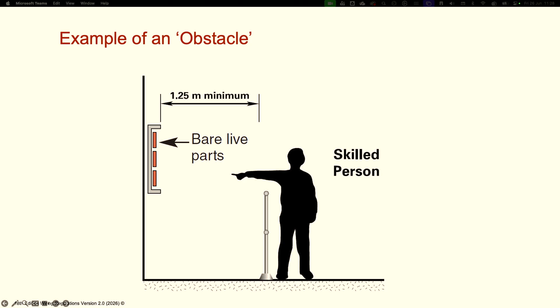If you go for an obstacle, you can have a particular type of object - not chairs, not boxes - but there'll be live parts on the wall. You would not design an installation like this today. This would be in an old switch room or transformer room. You can't just walk up to it - you should have an obstacle. You can climb over it, climb through it, even lift it out, it doesn't have to be bolted to the ground, but it's to prevent unintentional contact with the live part. So if you bashed into it walking back in the room, it would hopefully prevent you there. And the minimum distance is 1.25.